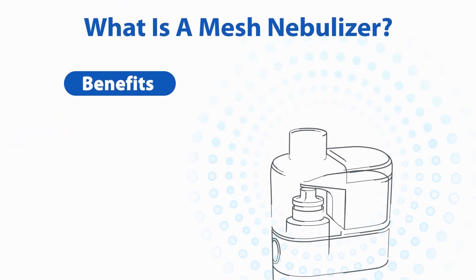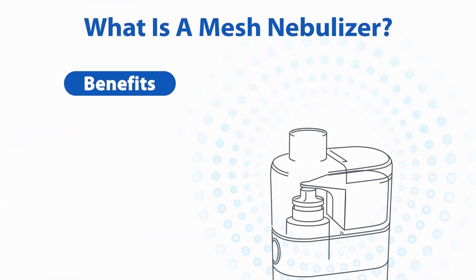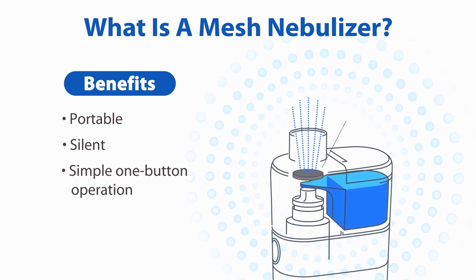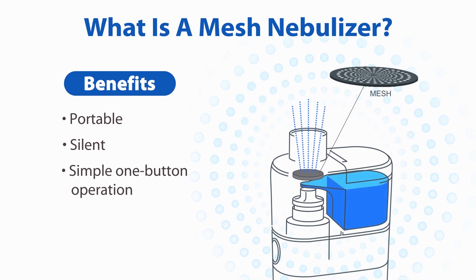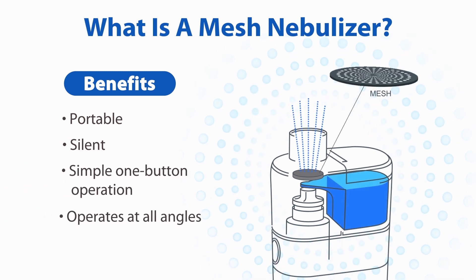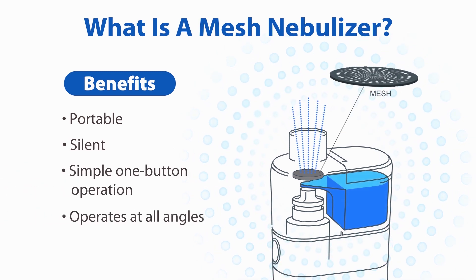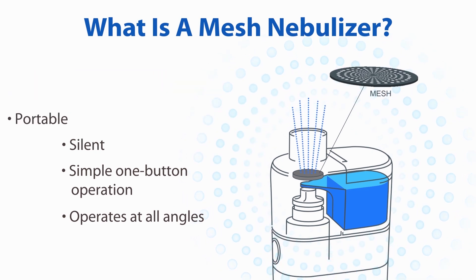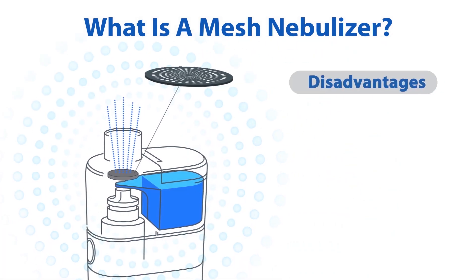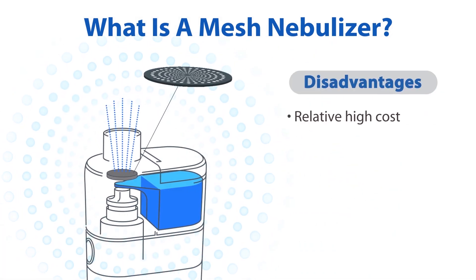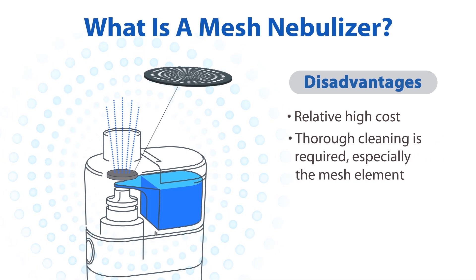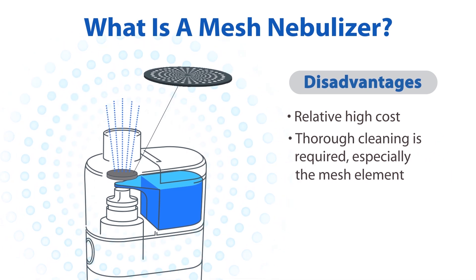However, the compressor nebulizer is usually bulkier, has many parts, is noisier, and requires a power outlet. Using mesh technology, mesh nebulizers are portable, quiet, and simple to use. They can also operate at all angles. Although superior in technology, mesh nebulizers tend to be more expensive and the mesh component requires thorough cleaning.